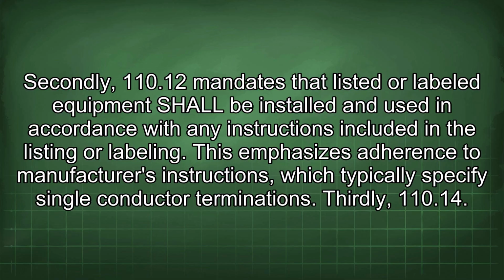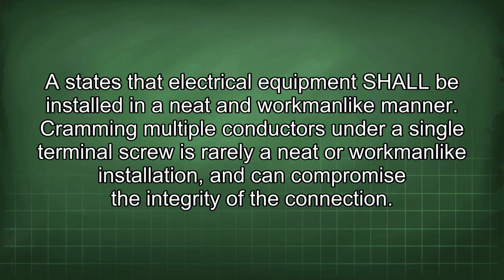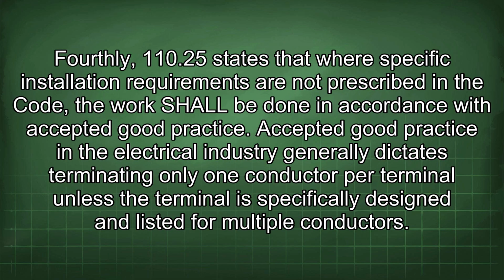Thirdly, 110.14. It states that electrical equipment shall be installed in a neat and workmanlike manner. Cramming multiple conductors under a single terminal screw is rarely a neat or workmanlike installation and can compromise the integrity of the connection. Fourthly, 110.25 states that where specific installation requirements are not prescribed in the code, the work shall be done in accordance with accepted good practice. Accepted good practice in the electrical industry generally dictates terminating only one conductor per terminal unless the terminal is specifically designed and listed for multiple conductors.